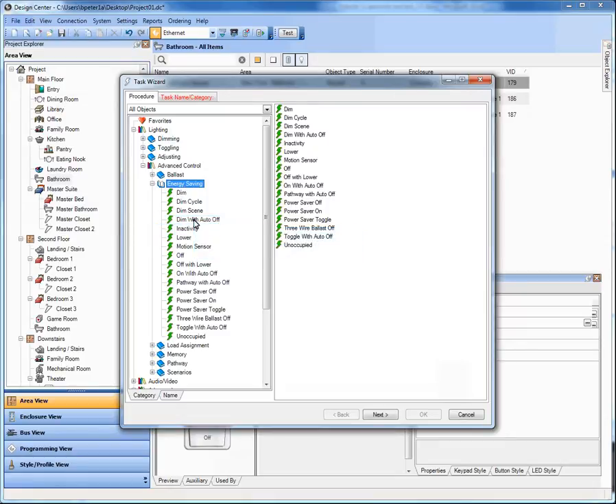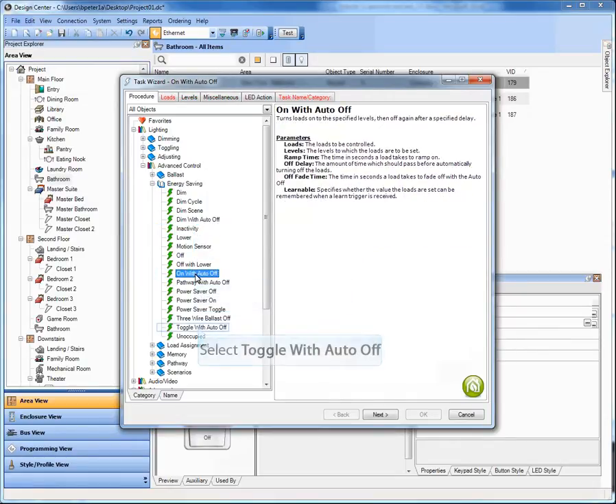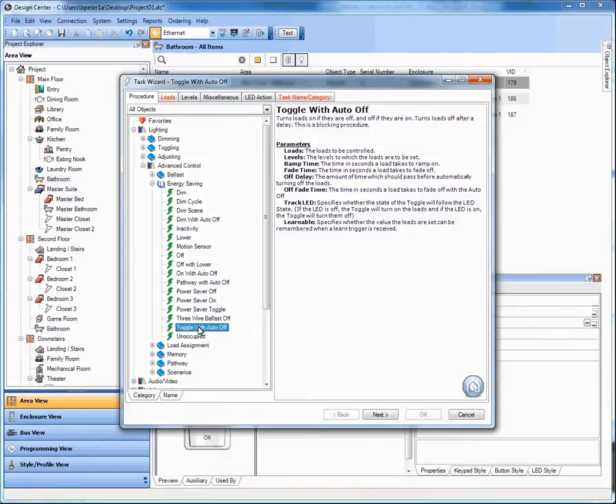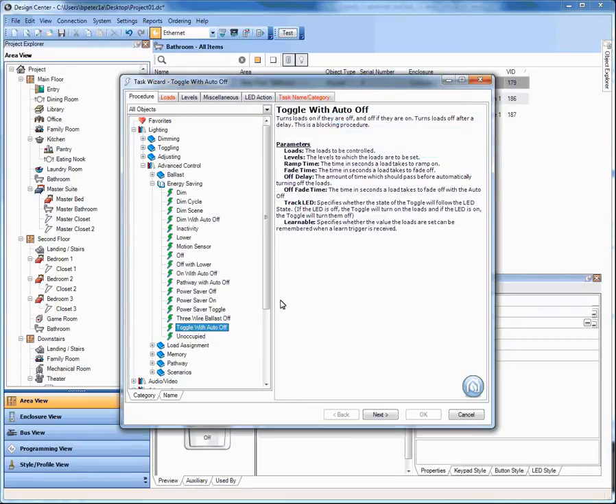So for 3.0 we've added dim with auto off, on with auto off, and toggle with auto off. In the case of this exhaust fan I'm going to use the toggle with auto off as opposed to the dim with auto off because I don't need to press and hold this load. It's not a rampable load. So I choose toggle with auto off.